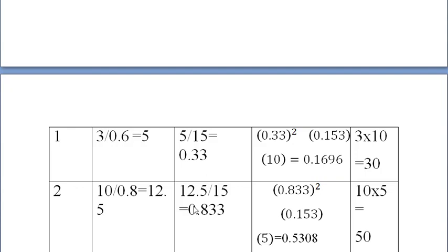So then we can calculate what is X, that is 12.5 divided by 15, where this 15 is the rated capacity of the transformer. So then we get here 0.833. Next, we calculate what is the copper loss in kilowatt hours. So we know X, so here it becomes X square, this is Wc in kilowatts, this is number of hours it is operated.